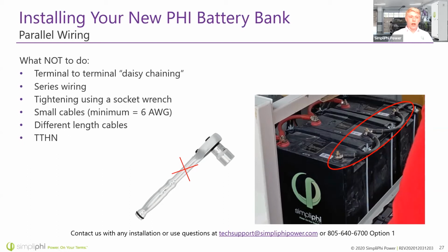Again, don't use a socket wrench and don't use small cables. Now, you can actually use THHN, there's no problem with it. However, I've just found it difficult to work with. It's not super flexible when you're maneuvering it into a connection point inside of a small battery box or combiner, and it's a little bit harder to crimp a large lug onto those, but it's electrically fine. I just prefer the flexible battery cables.